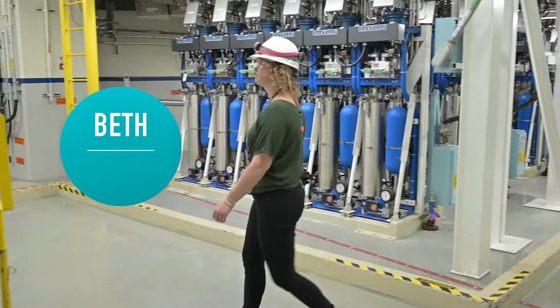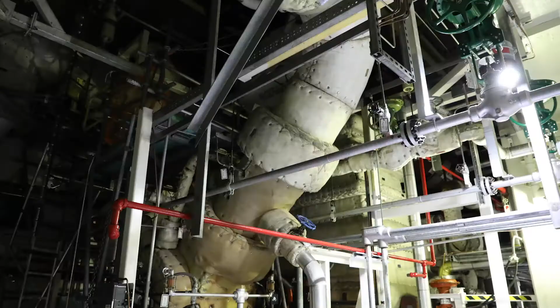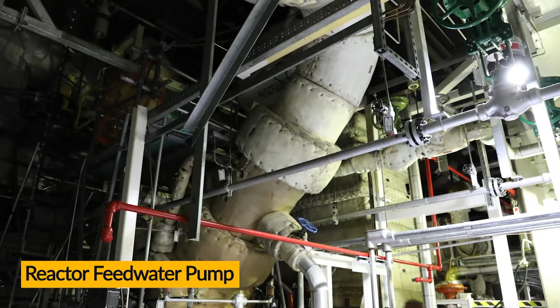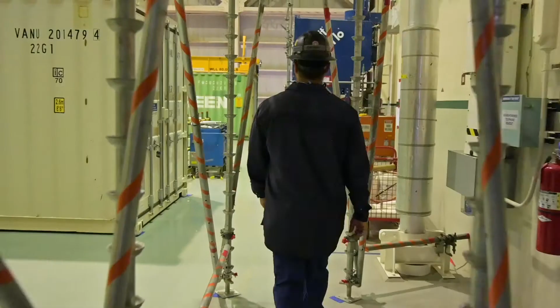Once the steam passes through the main condenser and returns to water, it collects in the hot well and is picked up by condensate pumps and sent through a series of filters and demineralizers. These large pumps are part of the condensate feedwater system, which supplies and preheats water to re-enter the reactor. They preheat the water from about 90 degrees to 450 degrees Fahrenheit. Once purified, the condensate booster pumps push the water to the feed water heaters and pump that water back to the reactor vessel.